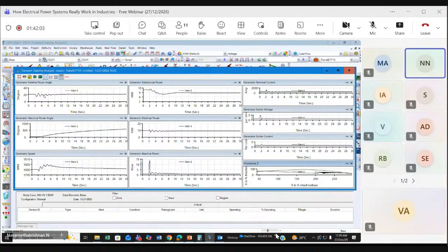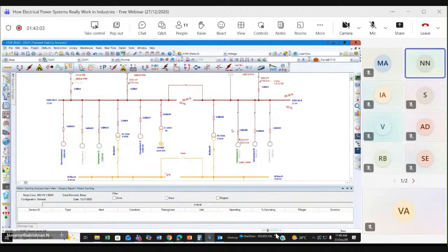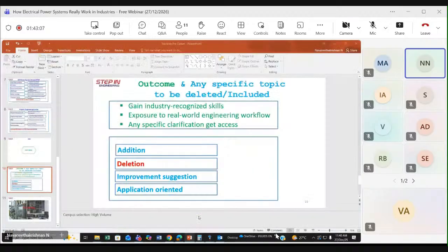The generator angle, power angle: you see the oscillation. You can see it is not much. It is going up to 21. It should quickly oscillate and settle. Otherwise, your generator will go out of step. You can see the megawatt. So in this, you can find out whether your system is stable or not, whether the generator is stable or not. See, during the fault, what is happening here? There's a jump. Okay, with that, I conclude this module, and I'll go back to my presentation here.